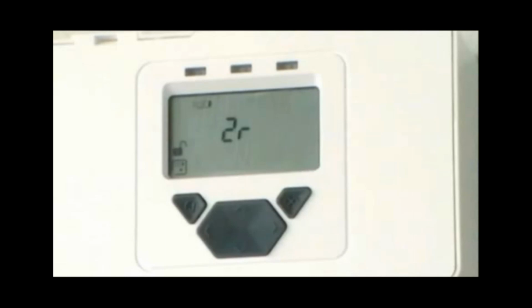The receiver icon at the top left of the display shows which receivers have been found. The display also shows 2R to indicate the number of receivers found. Press tick to accept the found receivers and to return to the Engineering menu. If the number of receivers found is not correct, retry by pressing the cross button on the system controller and reselecting Find or refer to troubleshooting in the installation guide.